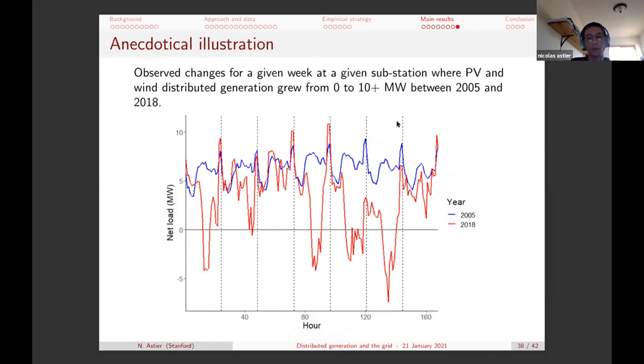And to give you a sense of what it means in practice, that's not a demonstration, that's pure anecdotal evidence, but if we take the substation I used as an example to explain what the load duration curve is and what the ramp duration curve is. So the blue curve I showed you was a given week in June for the substation in 2005. And now the substation has added over 20 megawatts of wind and PV. And that's what the load was in 2018 for the same week in June. And so you retrieve this feature that the impact on peak has not been significant, and you get these negative net loads, this very large swing in power flows. But that's just to give an intuition of the concrete impacts.